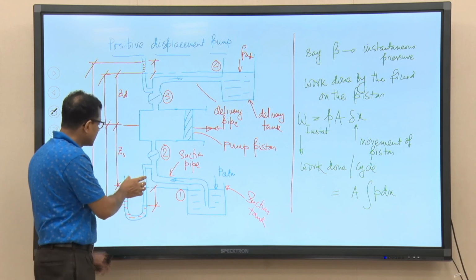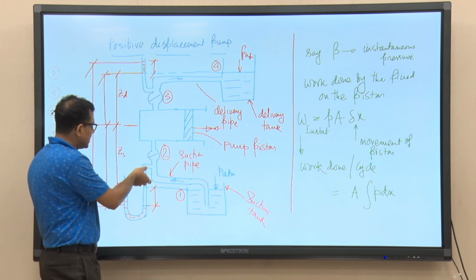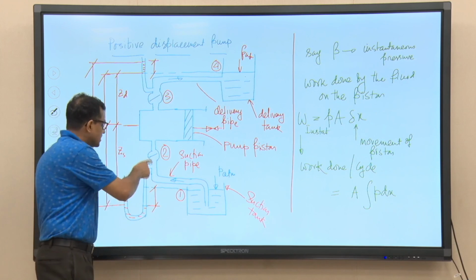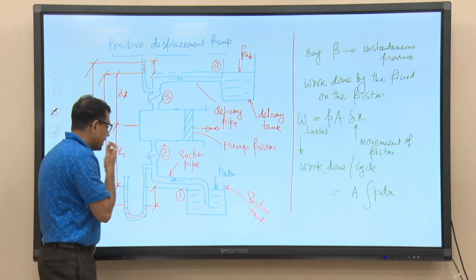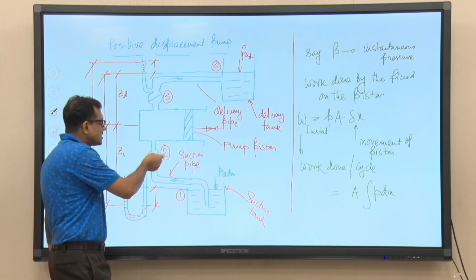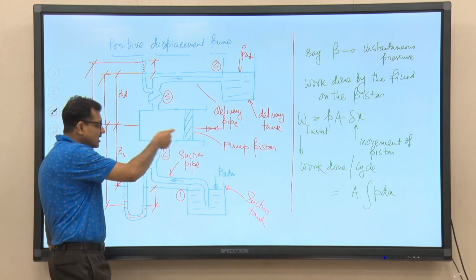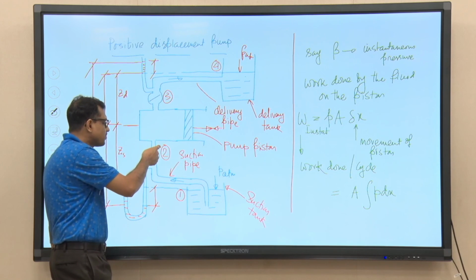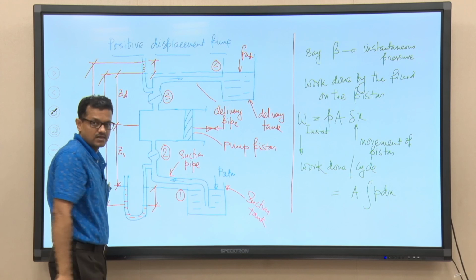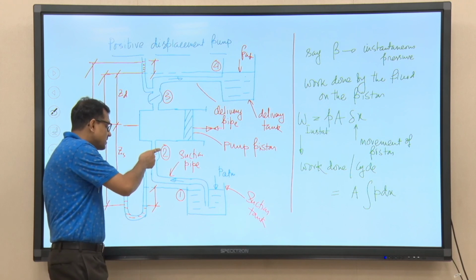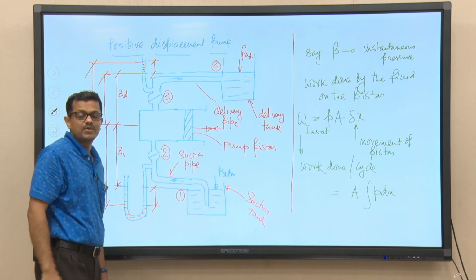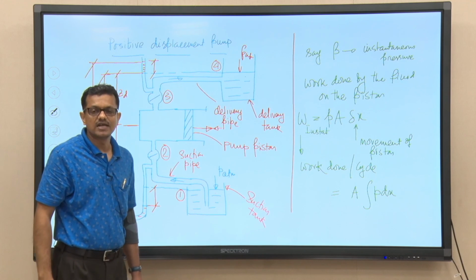In this circuit you have seen that we have shown a manometer that is connected to the suction pipeline. Now, the pressure inside this cylinder will definitely be less than atmospheric pressure. If that is the case, then pressure at point 2 also will be less than the atmospheric pressure, right. Now, if pressure at point 2 falls below the vapor pressure at that corresponding temperature, then cavitation will start, that we have studied.